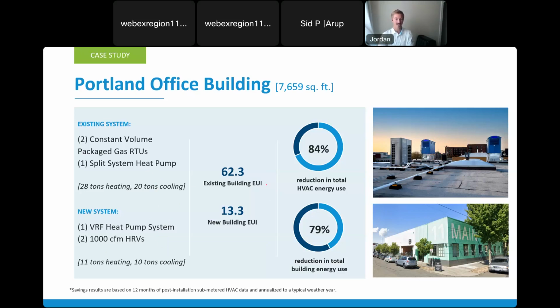From an energy standpoint, savings were drastic. 84% reduction in HVAC energy use, 79% reduction in building energy use. So ultra low EUI. No other measures outside of HVAC were done to get here. This is an old converted warehouse with uninsulated brick walls and single pane windows. So it's not like this is a fully modern ultra low energy building other than the HVAC system and the way it's controlled. So pretty significant results with just an HVAC upgrade.